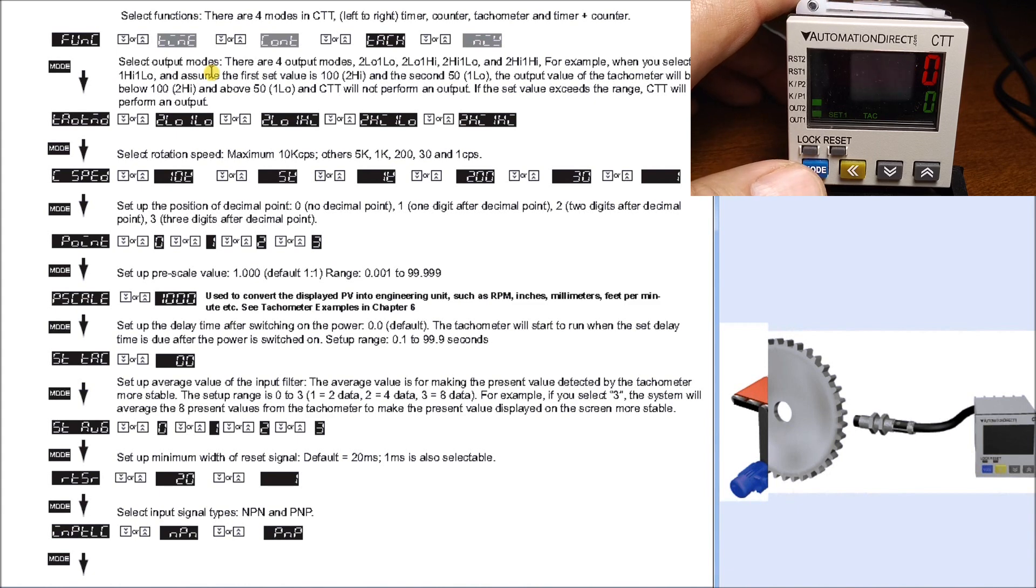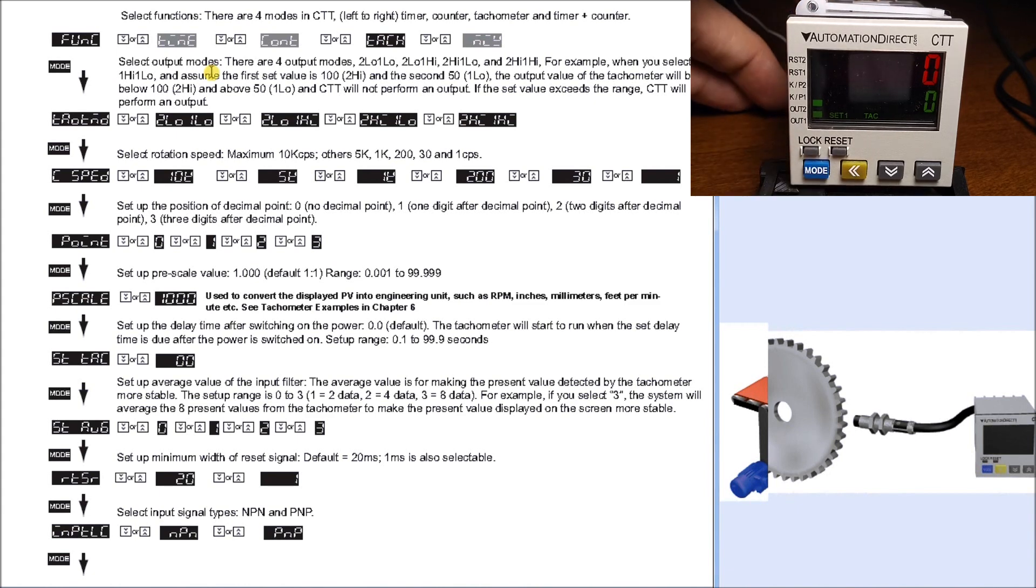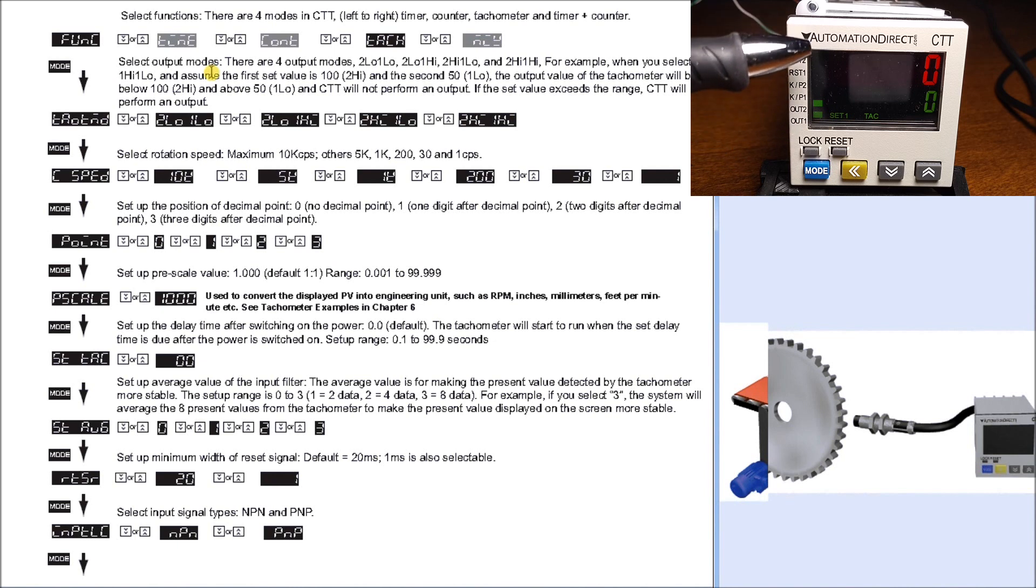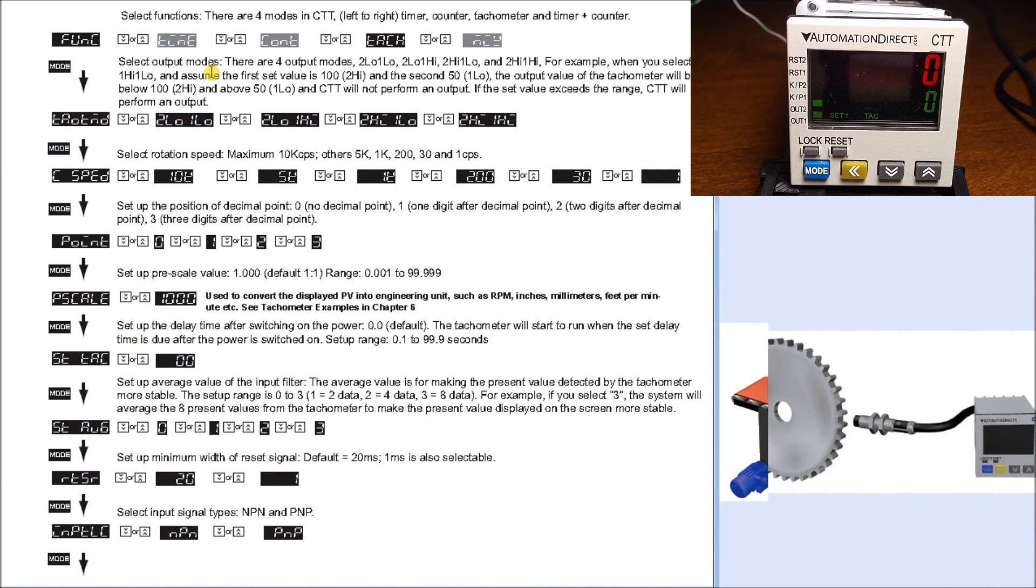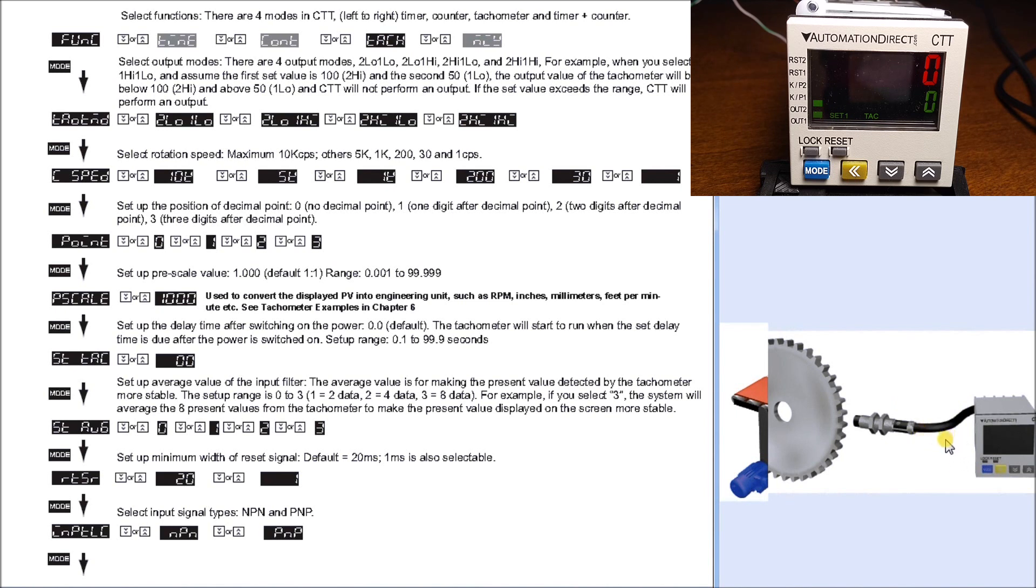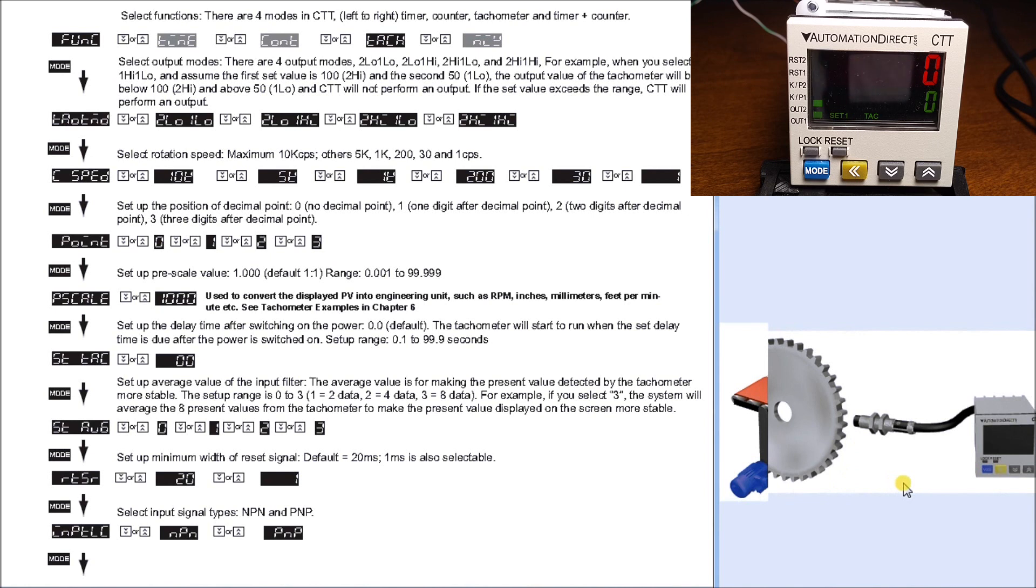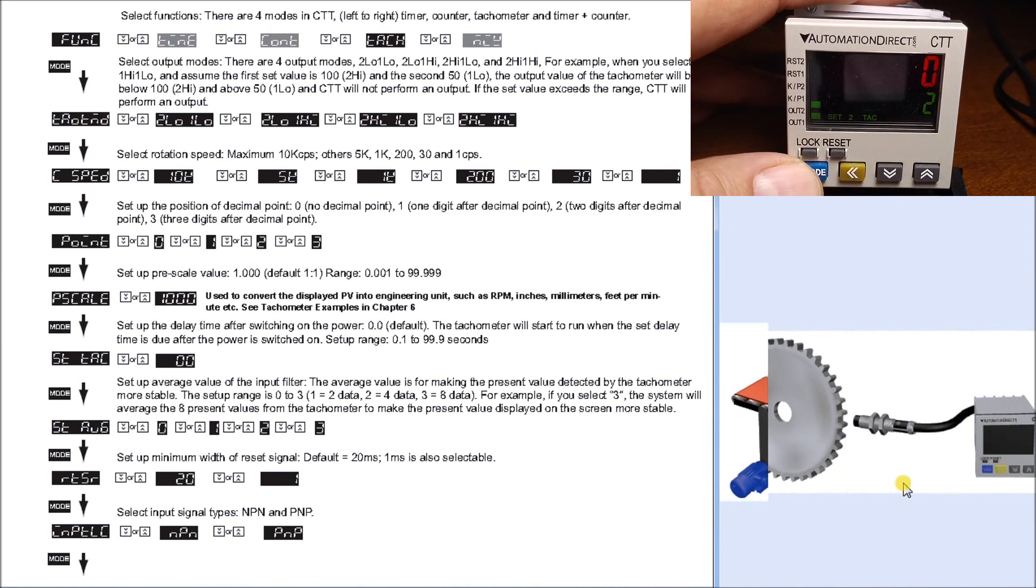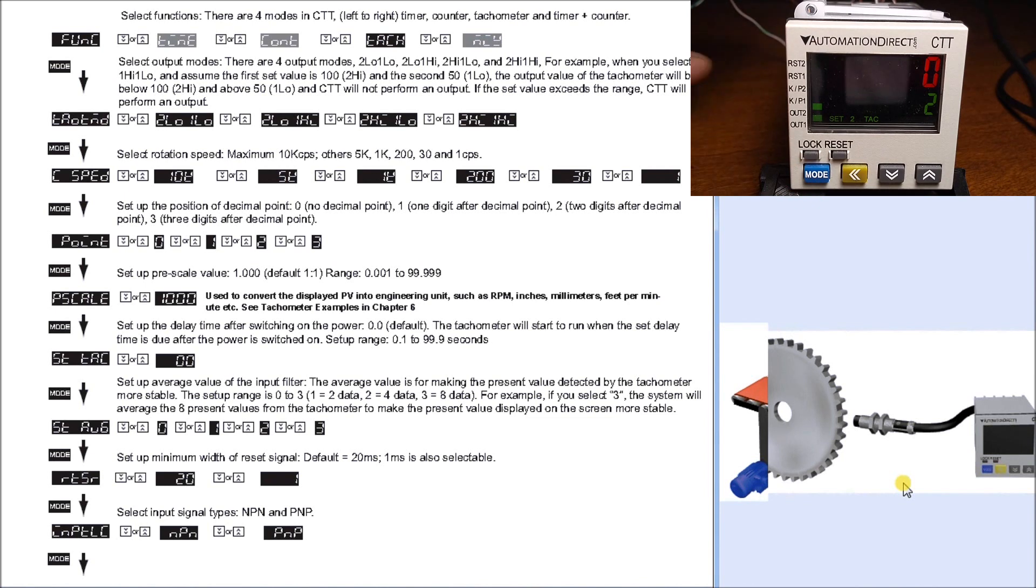Now we are running. You'll see on our screen both outputs are on right here. We have a set value of 1 of zero, so output 1 is zero. Because our tachometer value is equal to or less than that, we have output 1 on. Output 2 is again at zero, so it's on as well - it's not above that. If we hit the mode key, we'll see output 2 set value set for 2.